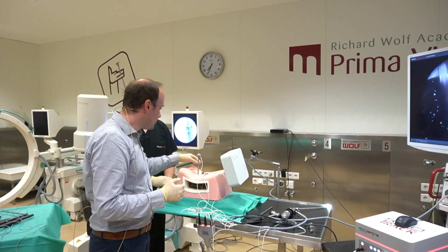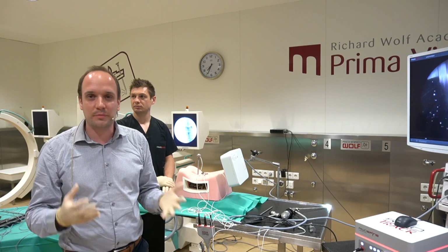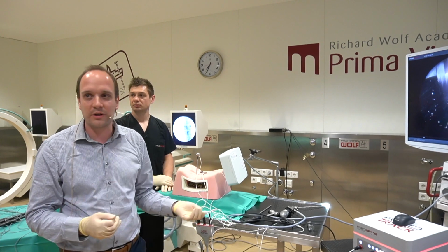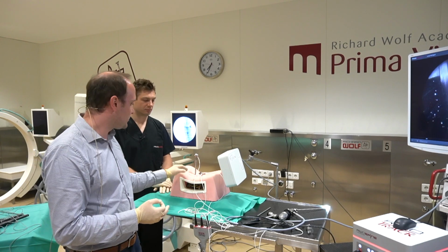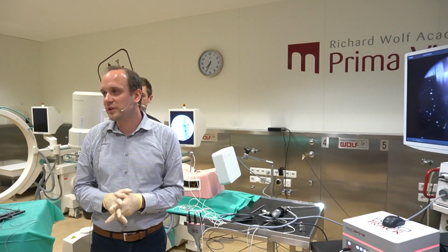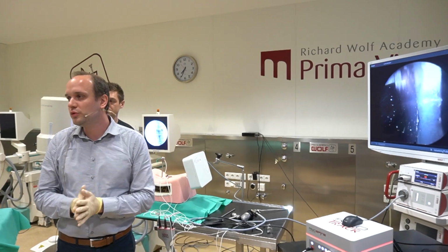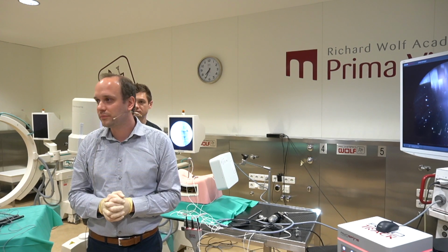What can happen is if you remove the K-wire after the calibration or after the patient referencing. If you remove the K-wire, of course, your patient reference has moved, and then the system doesn't know the referencing anymore. So that's the point. You should not remove the K-wire after the calibration. It has to stay exactly where it is.